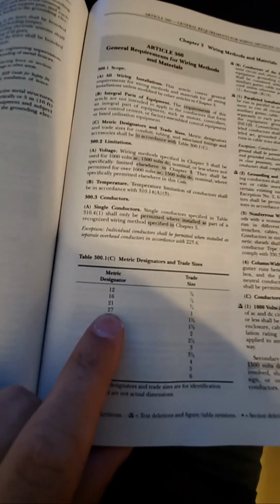So if I was to go through, this is a question that asks you about the trade sizes. This would be a question in journeyman's. 27 metric for a 1-inch pipe. Under metal corrugated roof decking, 1.5 inches, right there. That is one of your questions. Notches in the wood should be 1.25 inches, and the plate needs to be 1/16 inch thick. Let me find the 1.25 inch. Bored holes. Hang on. 1.25 inches right there. Right? Tells you how thick the plate needs to be.